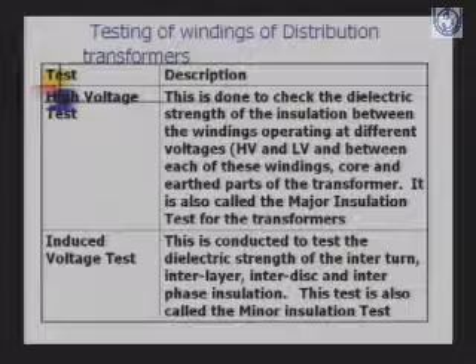So for the testing of windings of distribution transformers, there are many tests which are conducted. There is the high voltage test. This is done to check the dielectric strength of insulation between the windings operating at different voltages, HV and LV, and between each of these windings, core and earthed part of the transformer. It is also called the major insulation test for the transformers. Then there is the induced voltage test. This is conducted to test the dielectric strength of the interturn, interlayer, interdisc and interphase insulation. This is also called the minor insulation test. The high voltage test is known as the major insulation test. The induced voltage test is known as the minor insulation test.